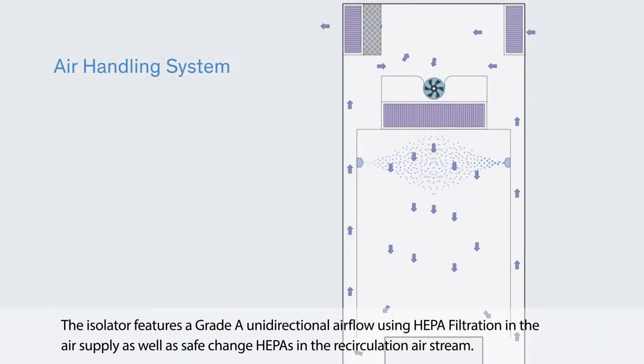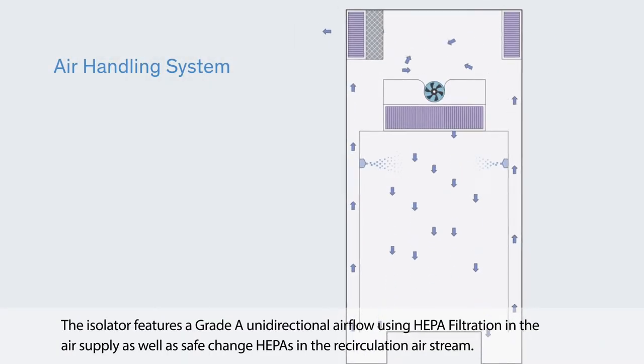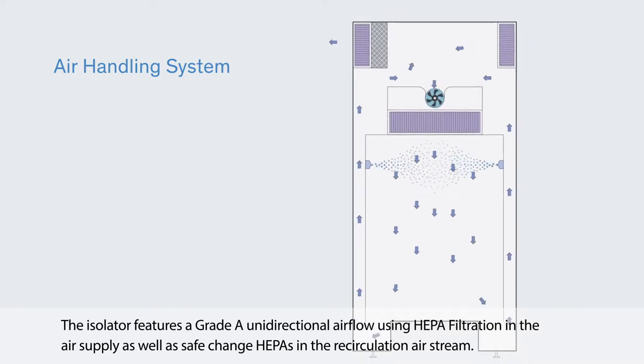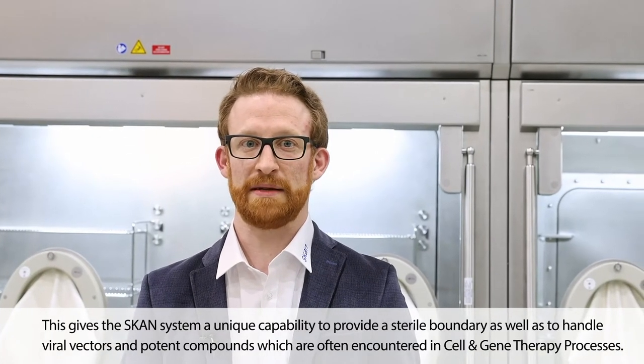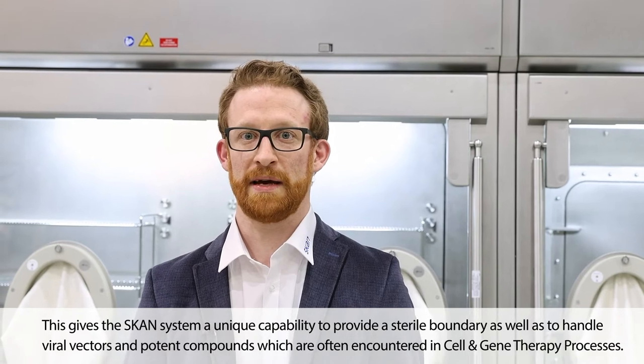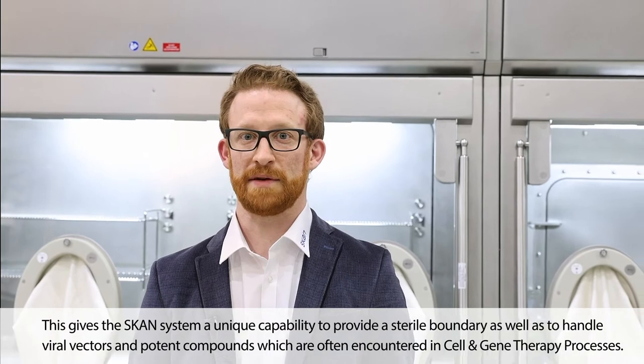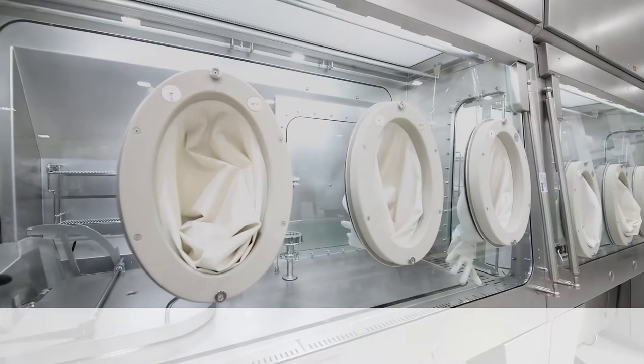The isolator features a grade A unidirectional airflow using HEPA filtration in the air supply as well as the SafeChange HEPA in the recirculation air stream. This gives the SKAN system a unique capability to provide a sterile boundary as well as to handle viral vectors and potent compounds which are often encountered in the cell and gene therapy process.